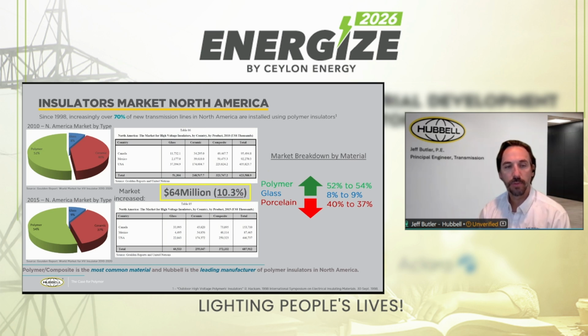So as far as in North America, that trend is much more accelerated in the use of polymer insulators across distribution and transmission voltages, and increasing. Hubbell recently supported a line, a 525 kV DC line that was polymer on the tangents, glass on the dead ends, but we're working on a 600 kV DC line that is going to be all polymer. So that just kind of speaks to the evolution of polymer insulators being accepted more broadly and at higher and higher voltages.